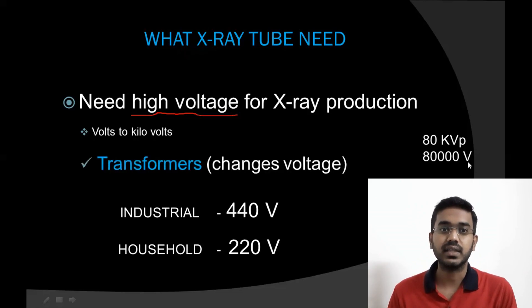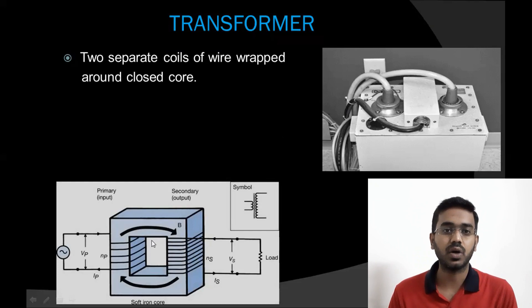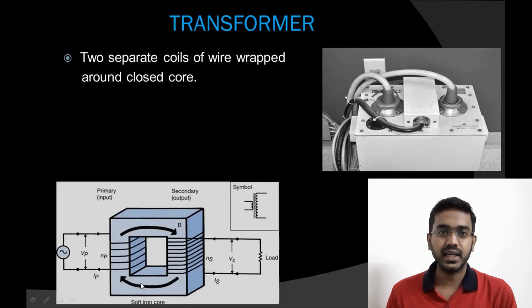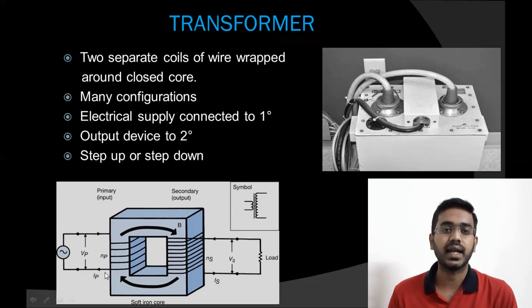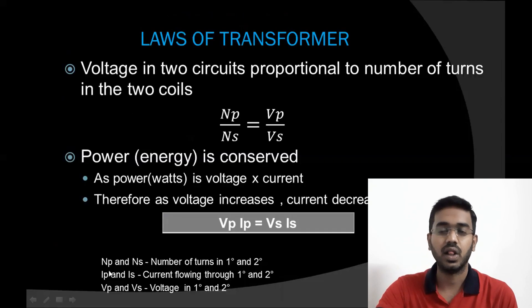A transformer is equipment that changes the voltage. Transformer looks like this — it has two separate coils of wire wrapped around a closed core. Electrical supply from the main source is connected to the primary side of the transformer, and the secondary side from the transformer is connected to the X-ray tube. Transformers have many configurations; based on this configuration, the transformer may be step-up or step-down. The voltage in the two circuits is proportional to the number of turns in the two coils.